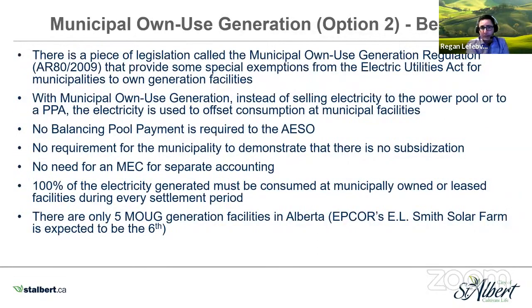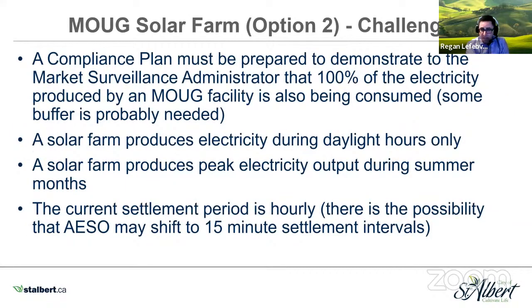Now I'll talk about municipal own use generation. There's special legislation providing exemptions for municipalities under the Electric Utilities Act. With municipal own use generation, instead of selling electricity to the power pool or through a PPA, the electricity is used to offset consumption at our own municipal facilities. There's no balancing pool payment, no requirement to demonstrate there's no subsidization, and no need for an MEC for separate accounting. However, 100% of the electricity generated must be consumed at municipally-owned or leased facilities during every settlement period. There are only five MOUG generation facilities in Alberta, and EPCOR's E.L. Smith Solar Farm is expected to become the sixth.